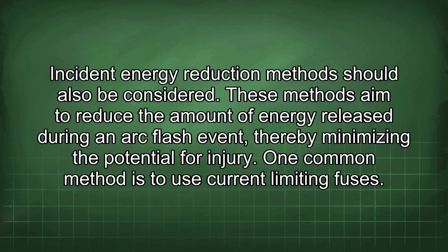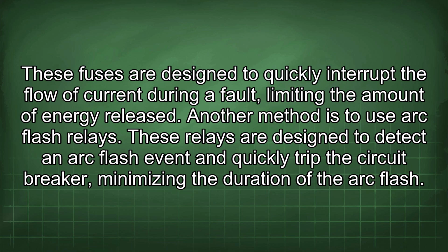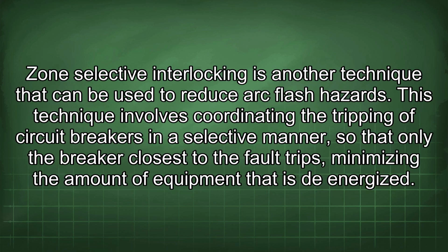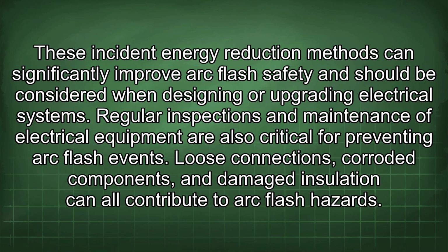Incident energy reduction methods should also be considered. These methods aim to reduce the amount of energy released during an arc flash event, thereby minimizing the potential for injury. One common method is to use current limiting fuses. These fuses are designed to quickly interrupt the flow of current during a fault, limiting the amount of energy released. Another method is to use arc flash relays. These relays are designed to detect an arc flash event and quickly trip the circuit breaker, minimizing the duration of the arc flash. Zone selective interlocking is another technique that can be used to reduce arc flash hazards. This technique involves coordinating the tripping of circuit breakers in a selective manner, so that only the breaker closest to the fault trips, minimizing the amount of equipment that is de-energized. These incident energy reduction methods can significantly improve arc flash safety and should be considered when designing or upgrading electrical systems.